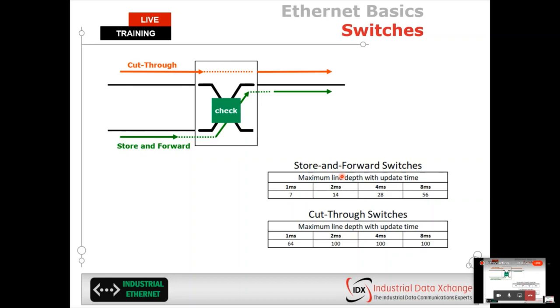So in store and forward switches, if I daisy chain these devices together, and each of those devices are sending data every 1 millisecond, that means I can only connect a maximum of 7 devices in this line daisy chaining topology. At 2 milliseconds, you can see as my update time slows down, I can connect more devices.